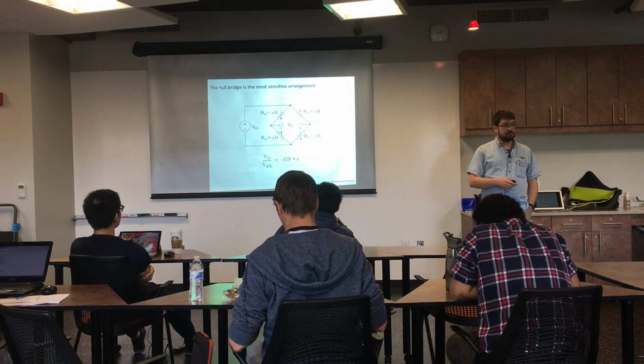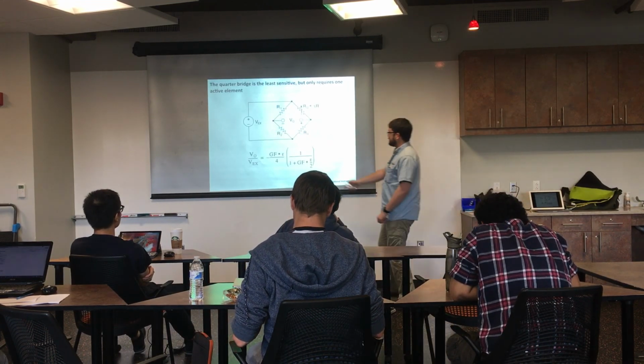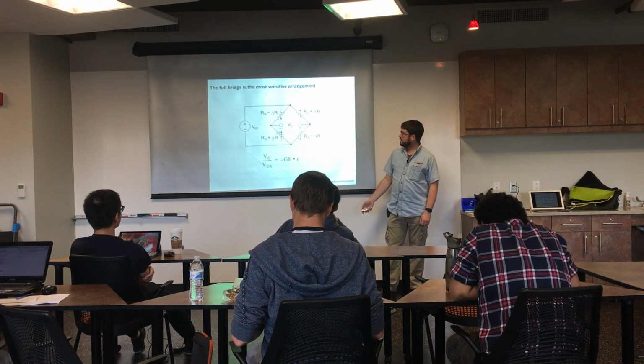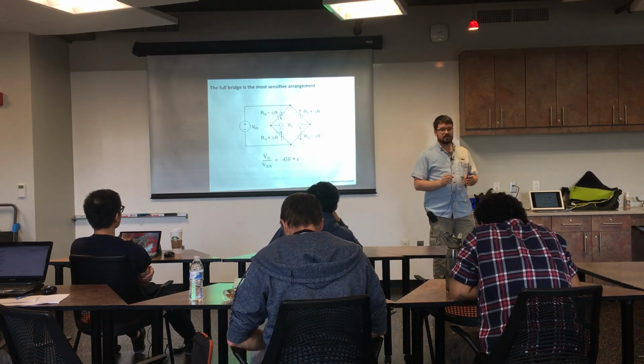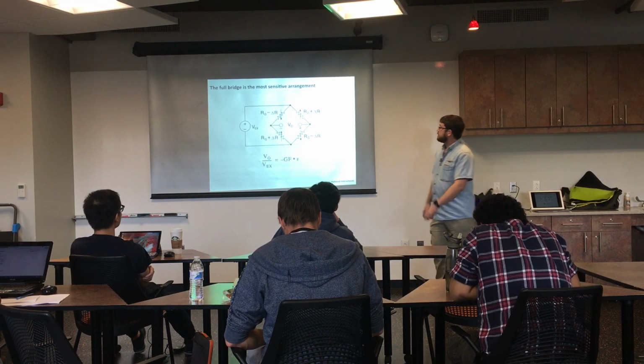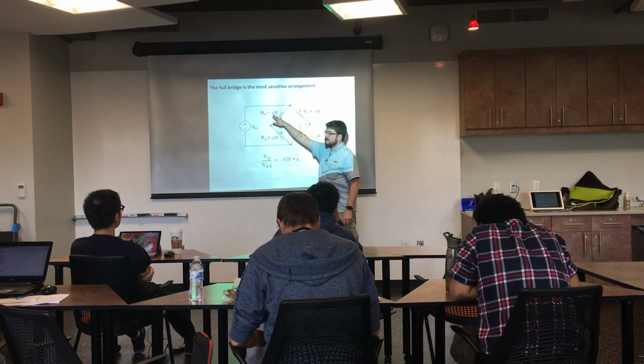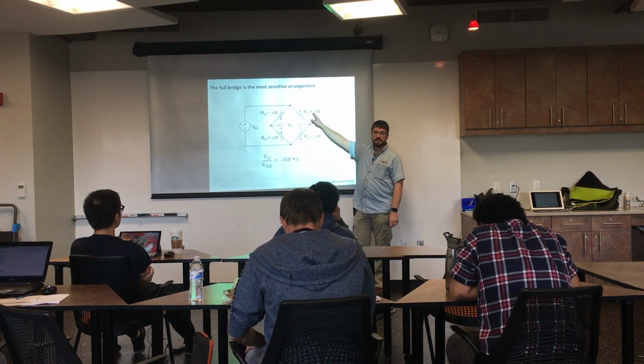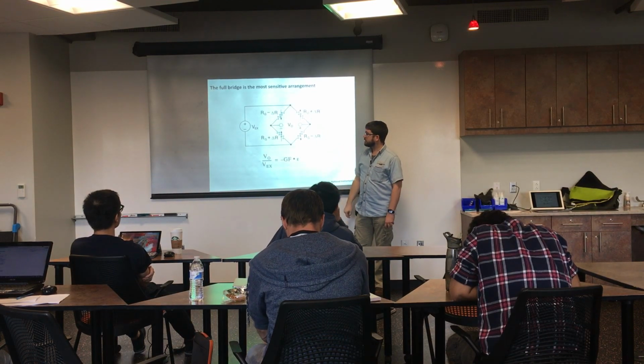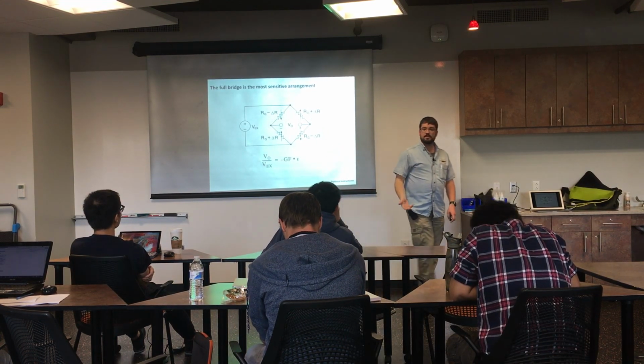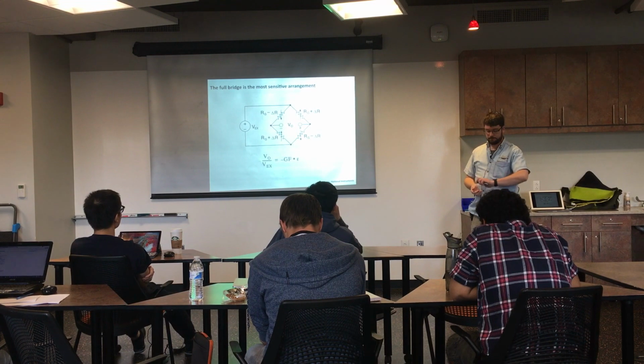The full bridge is the most sensitive arrangement. The denominator has kept shrinking, and now it's gone entirely. You've got 2 gauges that change with one sign, minus delta R, and 2 gauges that change with the other sign, plus delta R. This is what we use on load cells and similar devices in the laboratory.